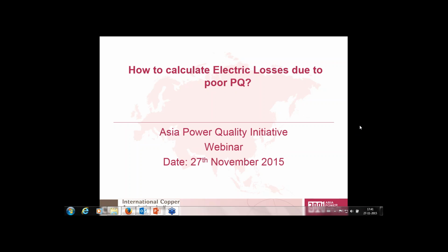If voltage reduces, of course, the total harmonic distortion certainly reduces. Or typically, a little increase in the load is also responsible for reducing the harmonics in the voltage. Let me read the question again. We know that the line current THD increases with increase in voltage across the motor. I'm not really aware that after a certain increase in voltage THD reduces. In general, we say that THD increases by increasing the voltage because of the saturation. Okay. Thank you.